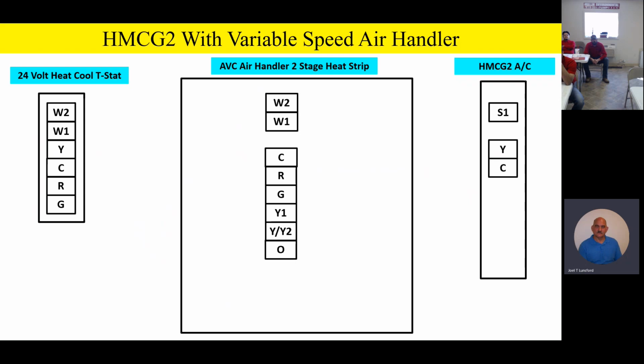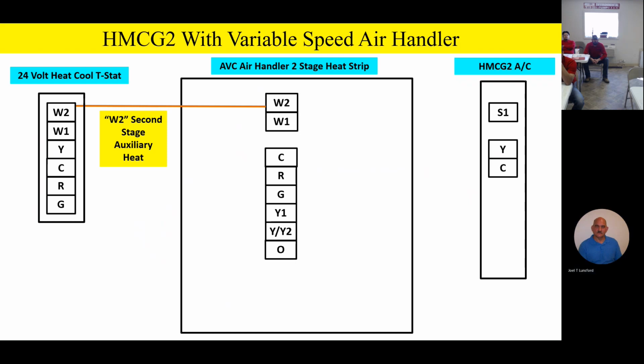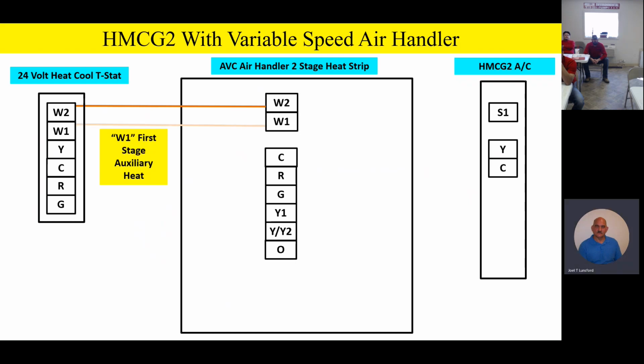But there's a little selector switch or a little jumper on the board itself that says heat pump, HP, or AC for air conditioning. Make sure that little jumper, that little dip switch, is in the AC position. That way, the indoor product ignores the O terminal. Other than that, it's pretty straightforward. W2 would be your second stage auxiliary heat. W1's your first stage auxiliary heat.